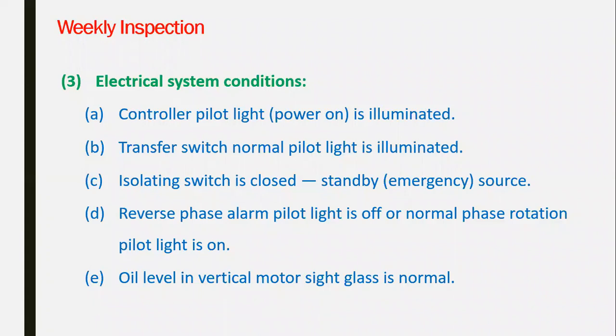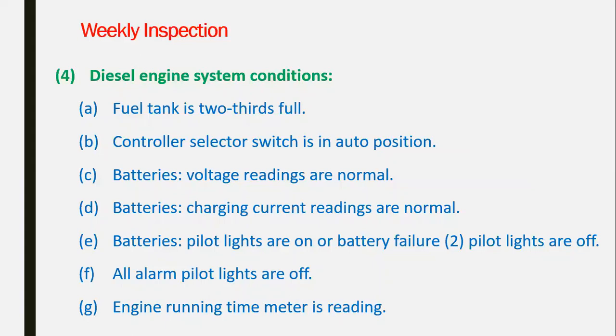So you can see here the electrical pump has a few steps and a few tests, 4 or 5 tests, visually weekly. On the other hand, the diesel: check that the fuel tank is 2/3 full. Why is it 2/3 full? Because when you go for the fuel tank, it has to be sized with 30% additional from the tank size required for operation of the fire pump for 2 hours. So 2/3 full is enough for the fire pump to work continuously.